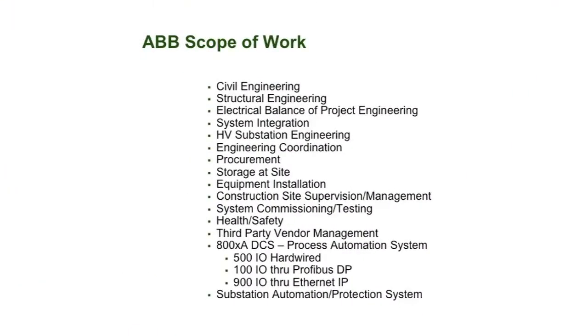The scope that we took on included the civil engineering, the structural engineering for the substation, the balance of electrical integration to pull that all together, the system integration, because we not only provided the micro-SCADA system to control the substation, we also provided the DCS to control the plant, and we tied those two systems together. But also tying in the UPSs with the generator, tying the medium voltage switchgear to the low voltage switchgear. We provided engineering coordination. We had a number of different engineering groups. We had substation engineering, civil engineering, structural engineering, low voltage systems. So we were responsible to bring all those different individual groups together to, again, provide the solution.